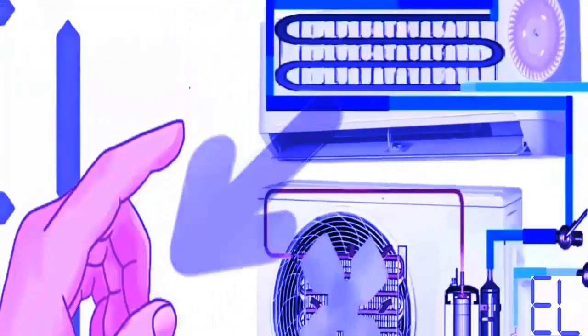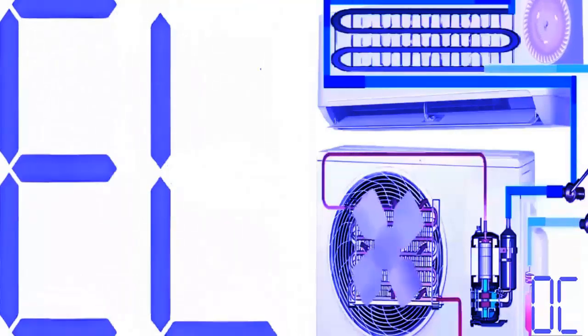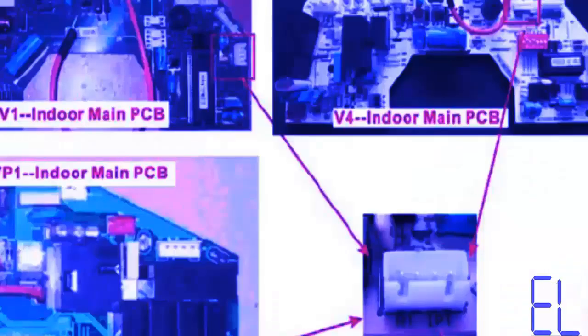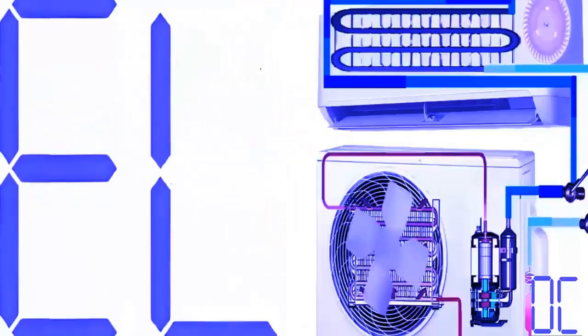4. To identify a potential false alarm, focus your diagnosis on the temperature sensor of the indoor unit's coil, or evaporator sensor. 5. Check the correct positioning of the sensor and the condition of the wires running from the electronic board to the sensor. 6. If the error persists, turn off the unit, disconnect the sensor, clean the connections, and reconnect it. Then, check again if the error continues to appear.